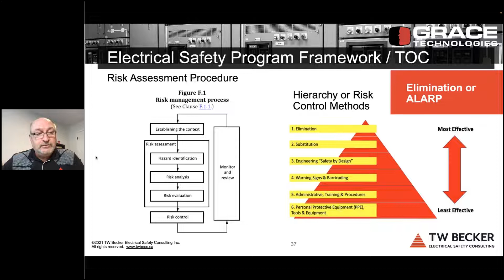Managing these arc flash hazard incident analysis studies and a report issued—arc flash incident analysis calculations, IEEE 1584, first published in 2002, new formulas in 2018. But unfortunately I'm still seeing reports come out where the labels include a hazard risk category number, a category number, a level letter, and they shouldn't, because there's no correlation between incident energy analysis and the arc flash PPE category method.